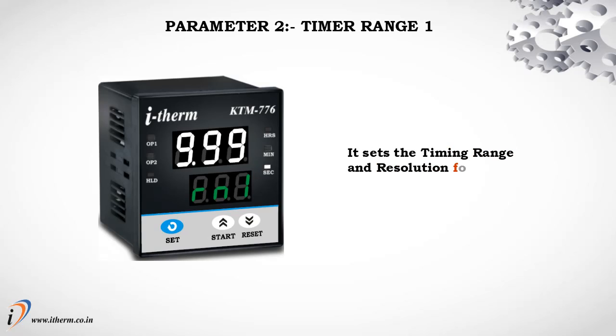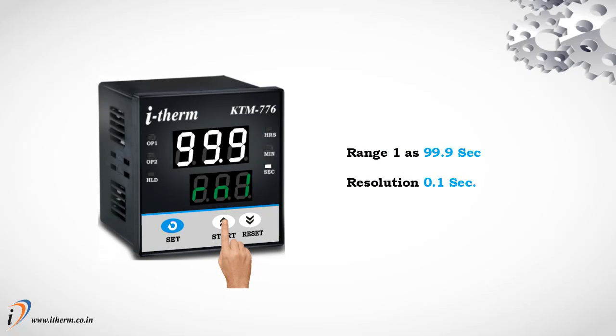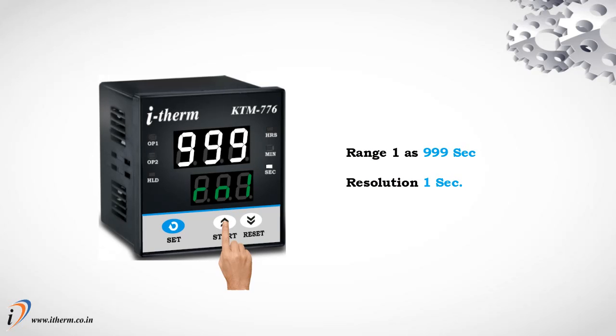Parameter 2: Timer Range 1. It sets the timing range and resolution for parameter Set Time 1. Range options: 9.99 seconds with resolution 0.01 seconds; 99.9 seconds with resolution 0.1 seconds; 999 seconds with resolution 1 second.